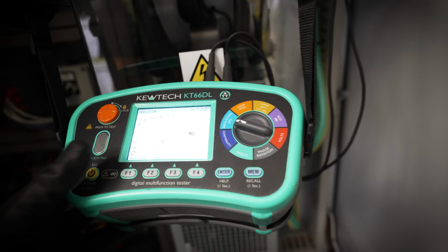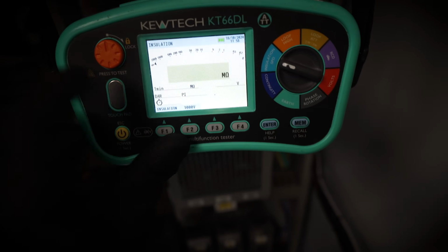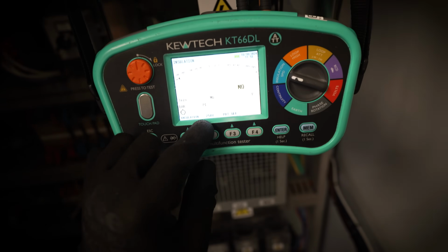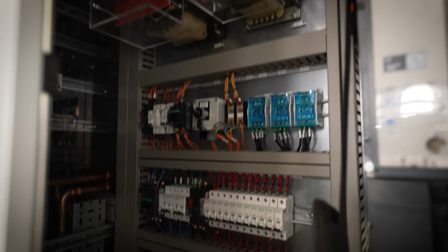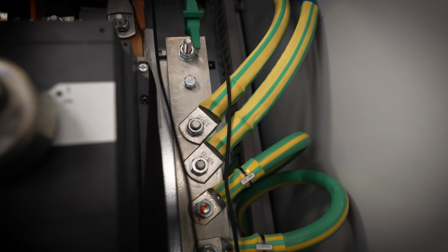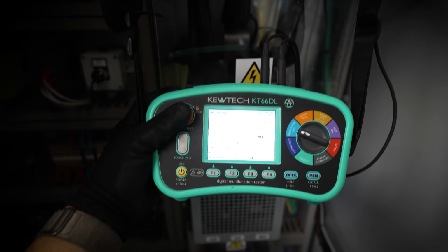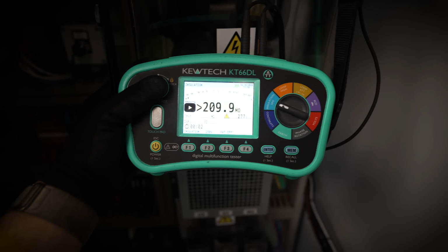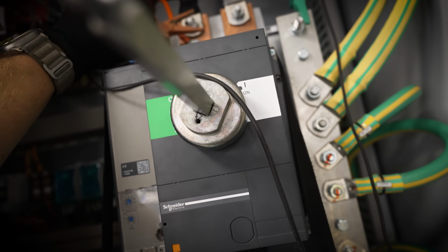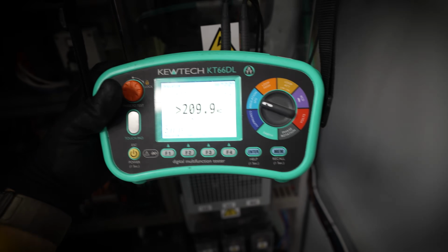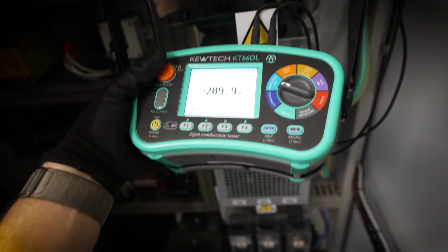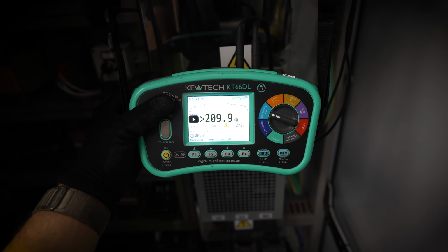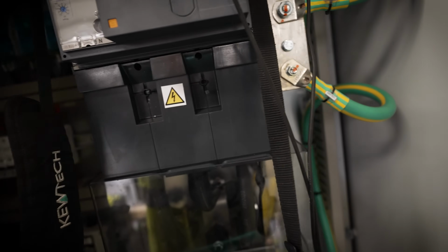So we want to jump onto insulation resistance. We want to drop down to 250 volts because we've got all sorts of electronics and stuff like that in here that we don't want to get freaky with. So we're going to start by going between all three phases and Earth. Greater than 209.9 megaohms. Greater than 209.9, lovely. So we're clear on them.